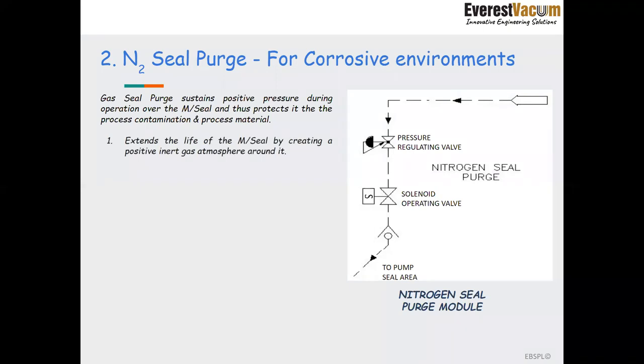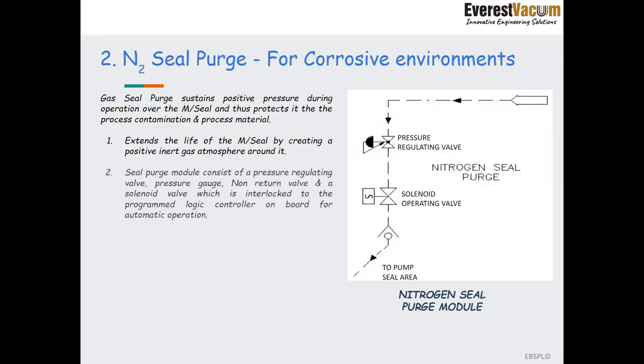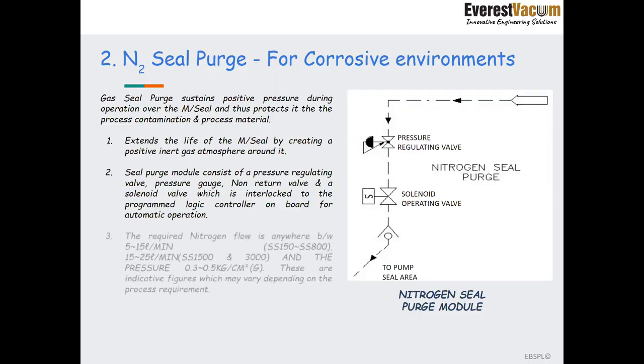So what does it do? It extends the life of the mechanical seal by creating a positive inert atmosphere around it. And it consists of a pressure regulating valve, non-return valve, and a solenoid valve, which is interlocked into the PLC, programmed logic controller, for the automatic operation.